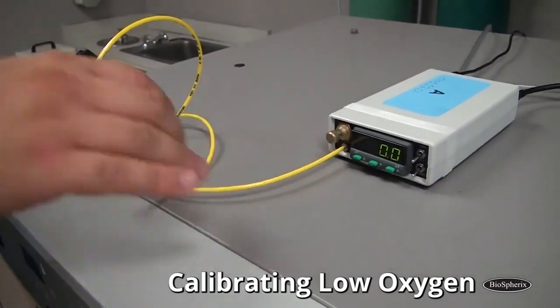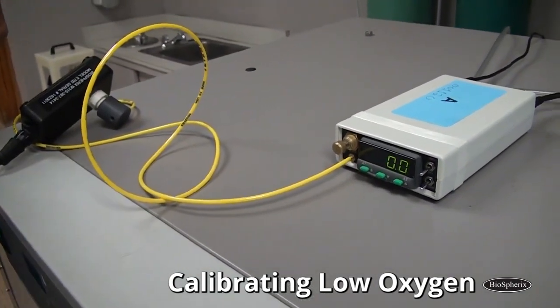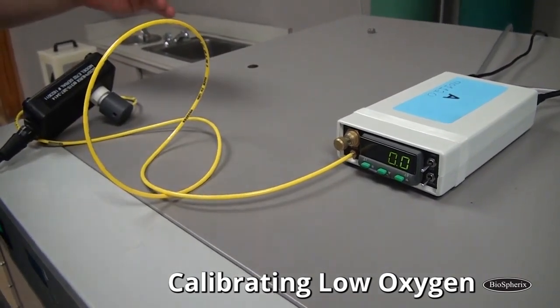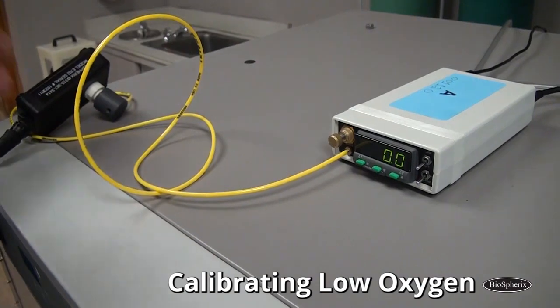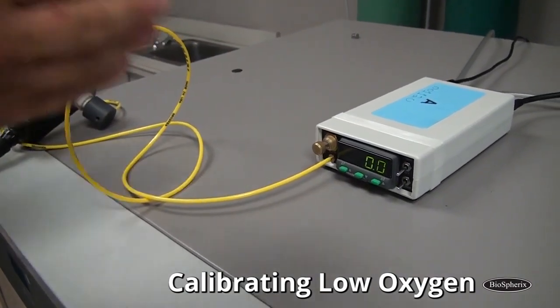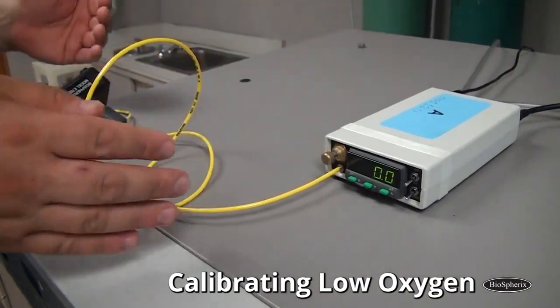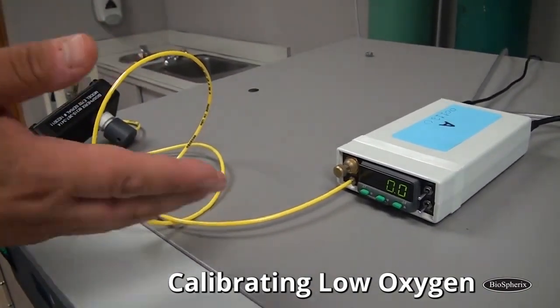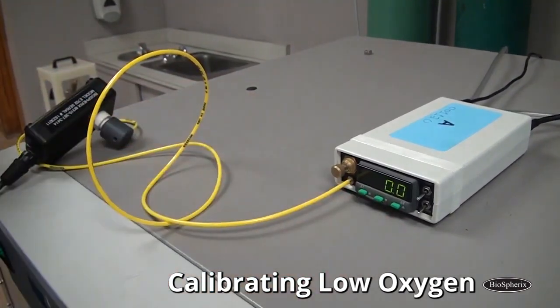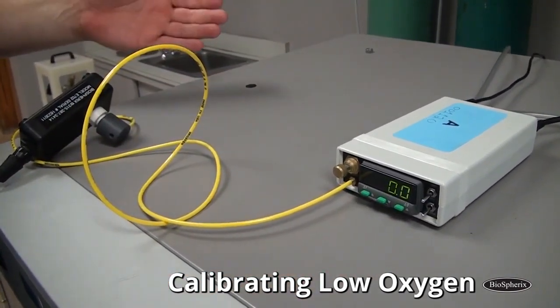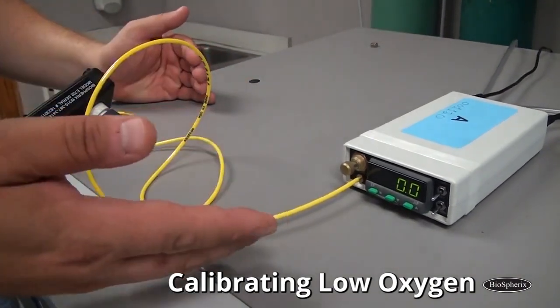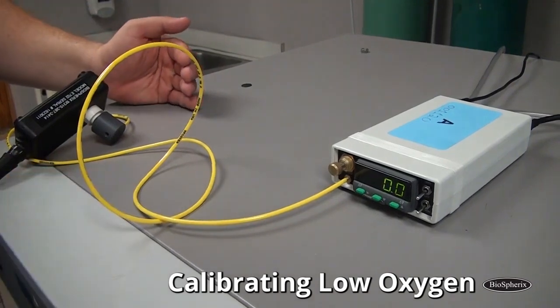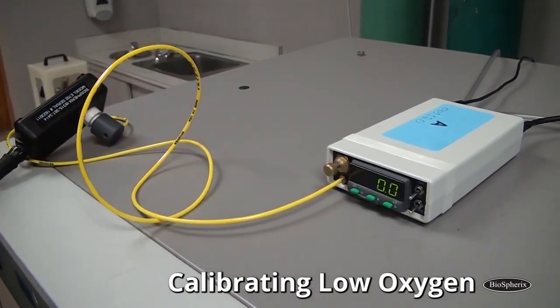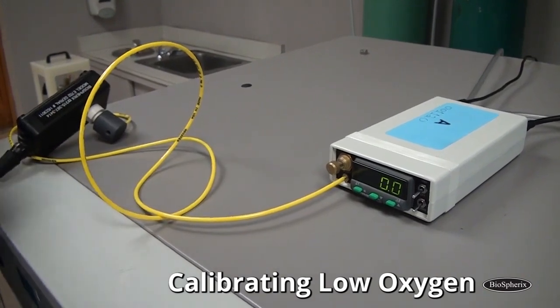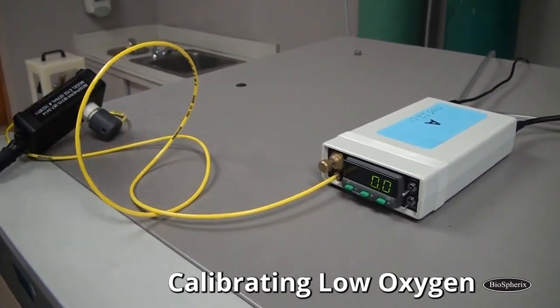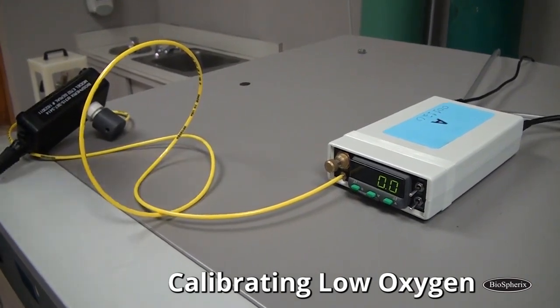When it stabilizes, make a note of how far off from 0.0 you are, because however far you are off, you need to make that opposite change to that coefficient, the 0 coefficient in level 3. So if it hadn't been 0.0, say it was 0.5, well, we know we're 0.5 above where we need to be, so we would have gone into level 3, found the 0 coefficient, and lowered that coefficient by 0.5. Whatever you change that 0 coefficient by, you change this reading exactly the same. It's a 1-to-1 change. So that's how you make your adjustment.